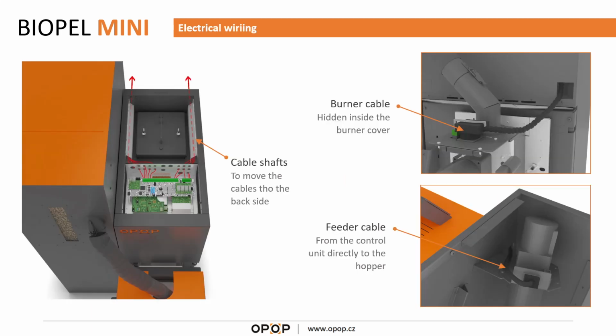Okay, so speaking of the control unit and electrical wiring, the control unit itself is on the top of the boiler. So you connect all the cables, all the temperature sensors here on the top, and then you move the cables from the top to the bottom. These plates can be removed, so you easily move the cables to the back side of the boiler and then cover the cables, protect them against heat and dust like this.